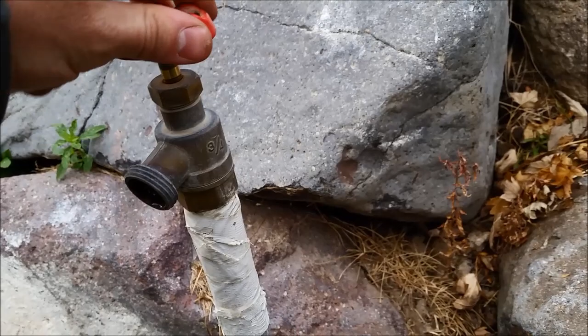Just to be aware, one year in the spring when we turned the water back on, this valve wouldn't work because sometimes the air pressure pushes up on a little rubber piece in this valve. We had to take the screw off the top and fix the rubber part that had been pushed up. So be aware, all that air pressure can cause issues with these screw-on rubber valves.